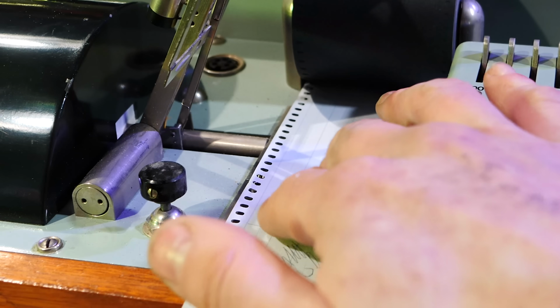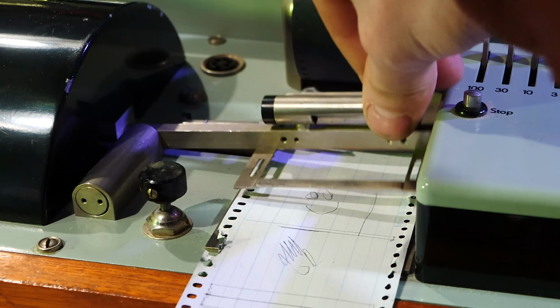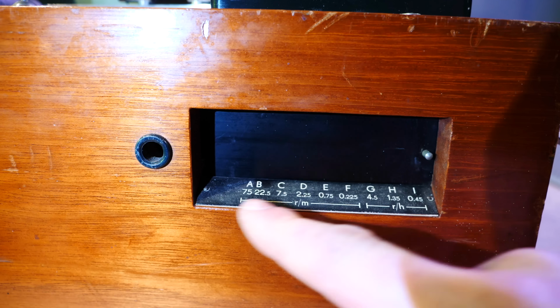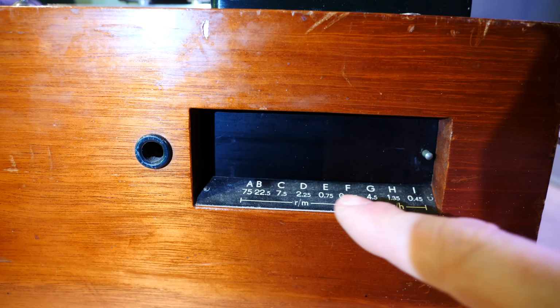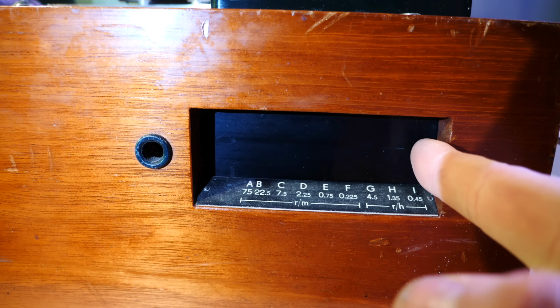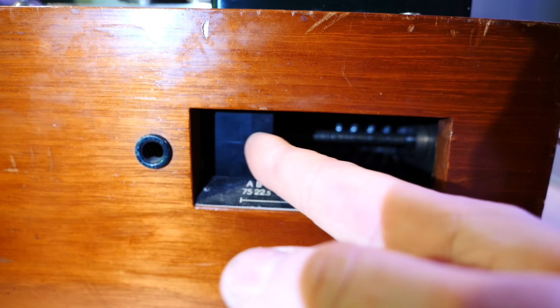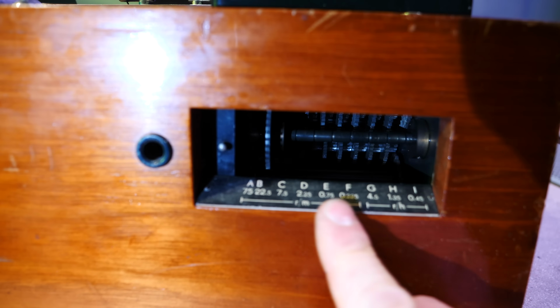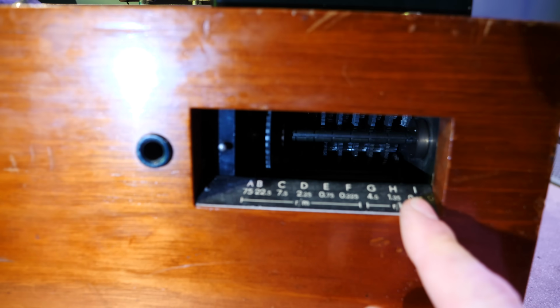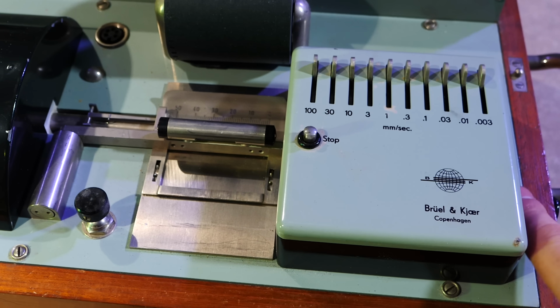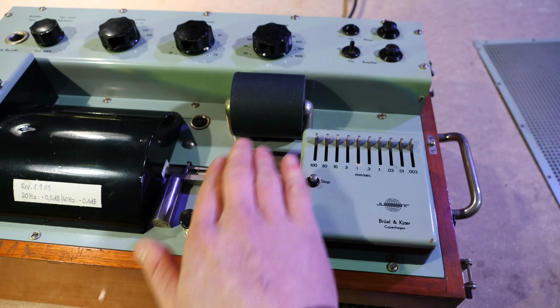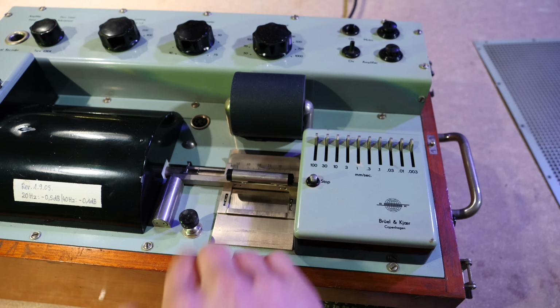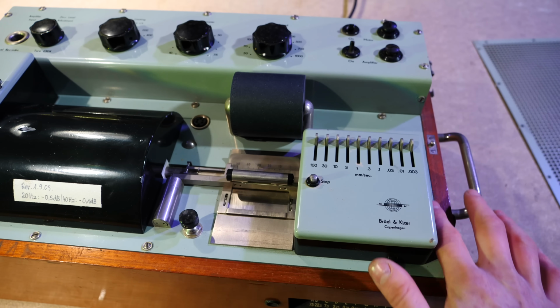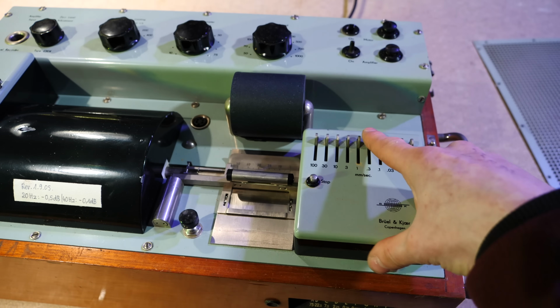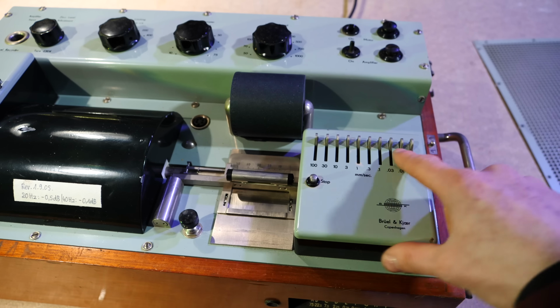Actually, you've got to make sure these are in line with the teeth. Oh yeah, it actually has a calibration window in the front that lets you record the rotations of the gears inside the driving gears. You can see the gears moving and it tells you the speeds that they should be running at, so you can adjust things accordingly. When I twist the drive shaft, you'll see these teeth move. These teeth feed the chart paper through the recording device. And yeah, I can basically engage a certain speed and you'll see these teeth moving in time.